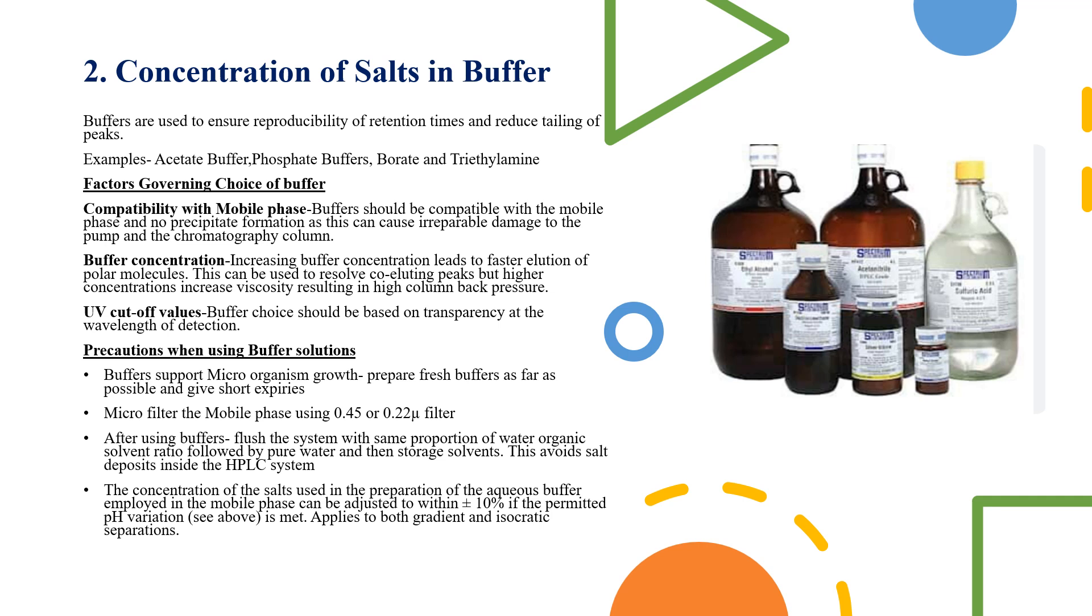Then ensure that you filter your mobile phase through a 0.45 or 0.22 micron filter. Then after using the buffer, flush the system with the same proportion of water and organic solvent ratio, followed by pure water and then storage solvents. This is to avoid salt deposits inside the HPLC system.